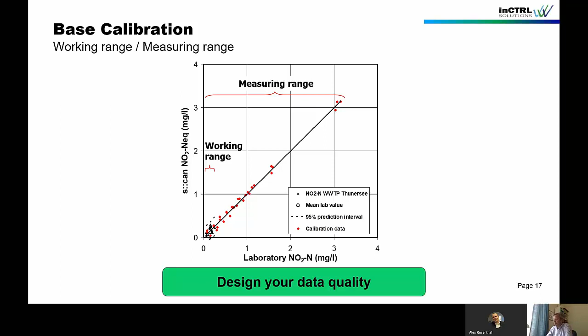What we actually introduced is an initialization phase where we spend quite some time collecting enough data points to confirm that the sensor is properly calibrated and working. On the x-axis you see the lab value, on the y-axis the sensor value, and the green line is where you want all the measurements to be.